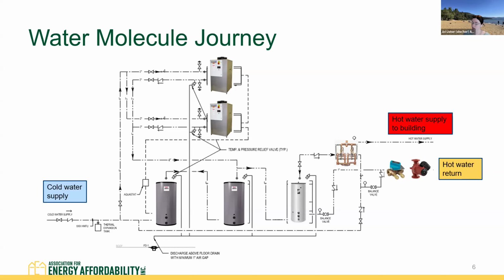We're all charged up. So then, when someone turns on their fixture in their apartment, we've got demand on the system, and that water molecule will be drawn up from this storage. It comes through the swing tank and over to the mixing valve. Remember, at 140 degrees, that's too hot to be supplied to the building. So we're also going to mix it with cold water here from the cold water supply down to our supply temperature of 120 degrees.